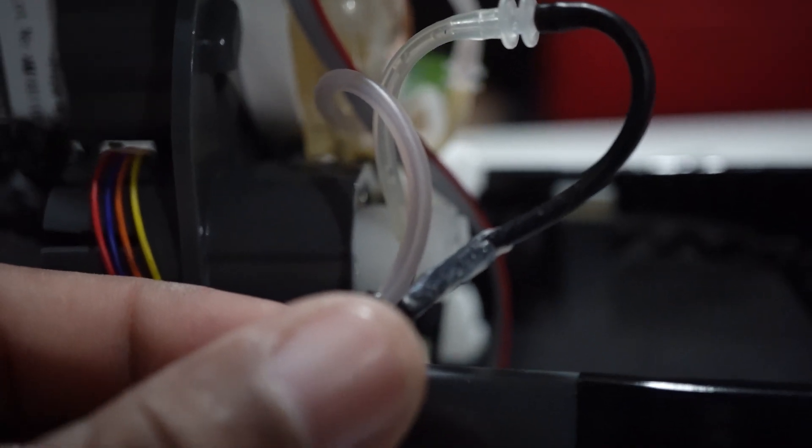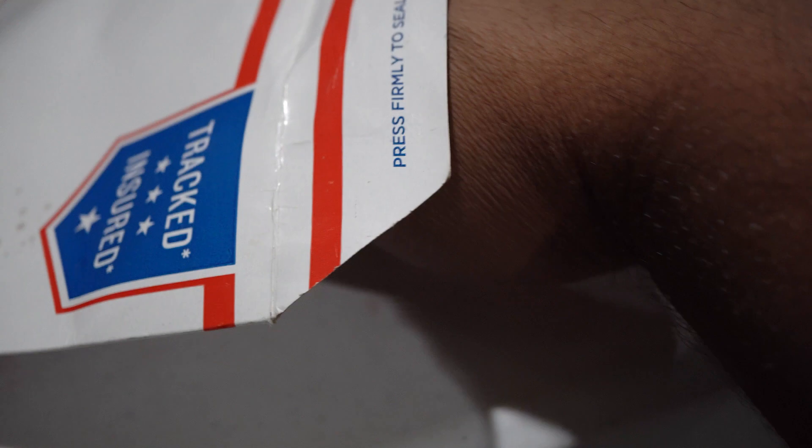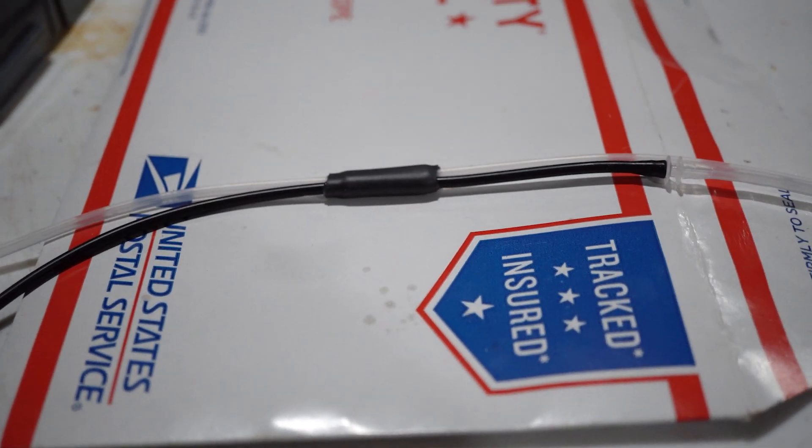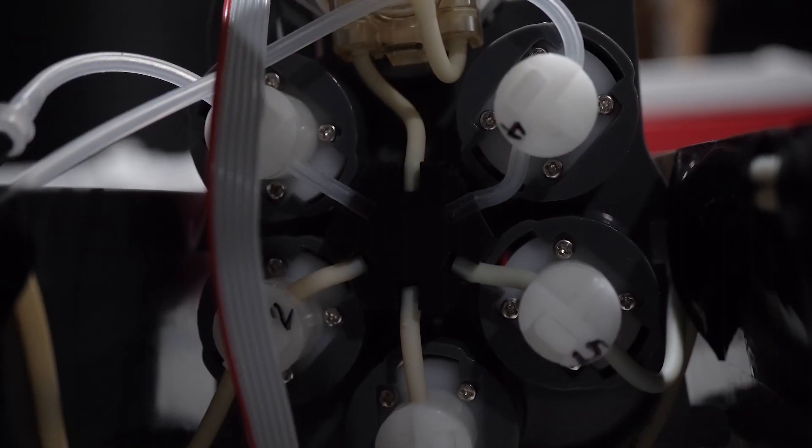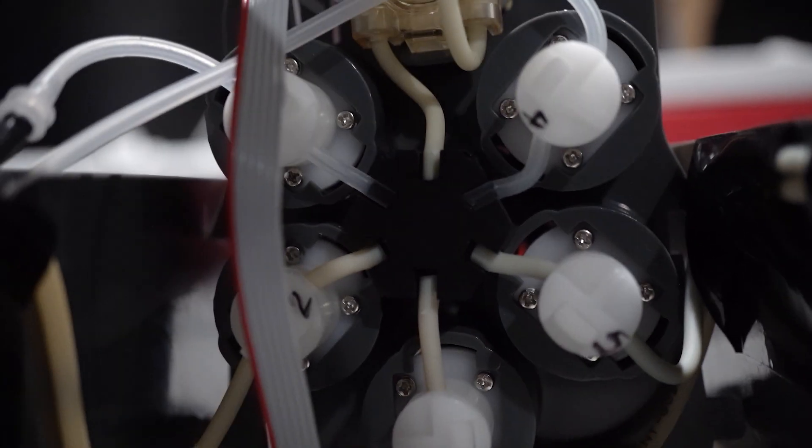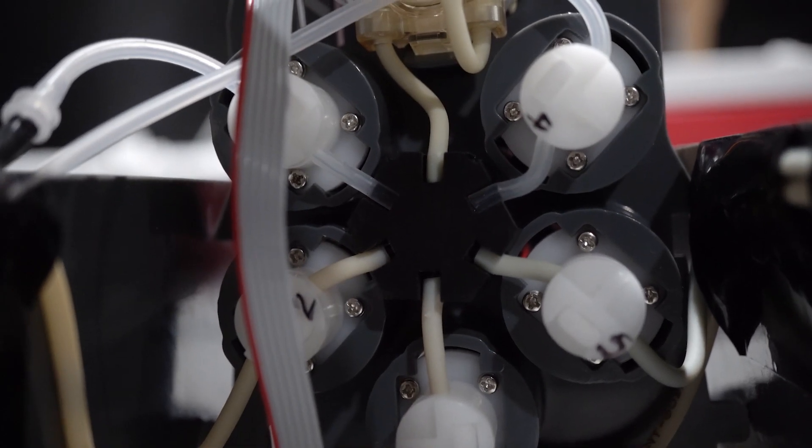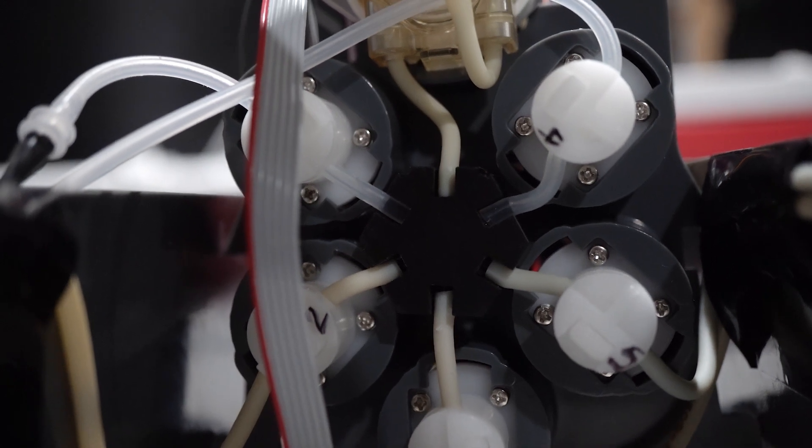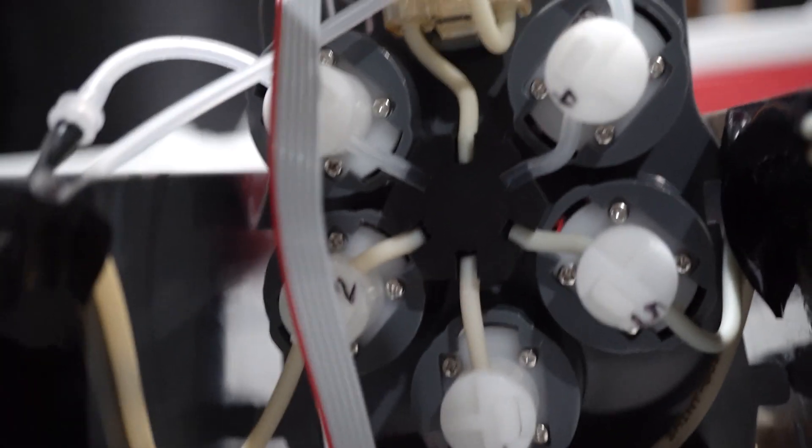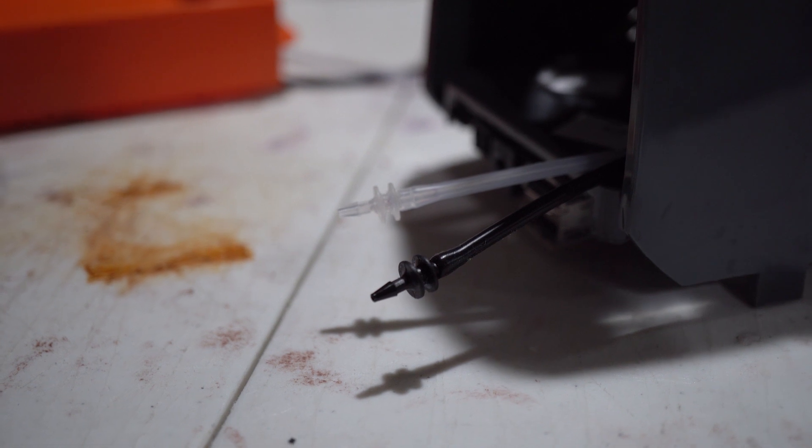Among other things, my fix would be to replace this tubing assembly with the new one that was sent to me. But for my particular fix, I just simply disconnected the existing tubing setup and replaced it using the same tube routing that was already there and present. The most difficult part was connecting the new tubing to the star connector. That's that little star portion right in the middle. There's very little tolerance here, so you definitely have to take your time and make sure that you have enough slack in order to plug it in. Small fingers make this a really easy job.